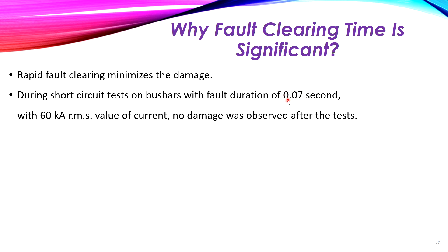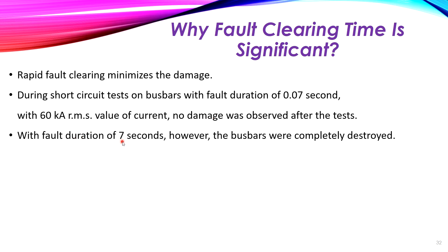During those 0.07 seconds, the relay and circuit breaker operated and cleared the fault. With 60 kilo-amperes at 0.07 seconds, no damage occurred to the bus bars. However, when the fault duration was allowed to reach seven seconds at the same 60 kilo-amperes, the bus bars were completely destroyed. This means we should clear the fault as soon as possible to prevent equipment damage.